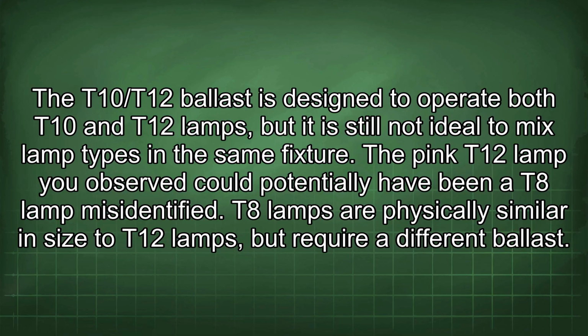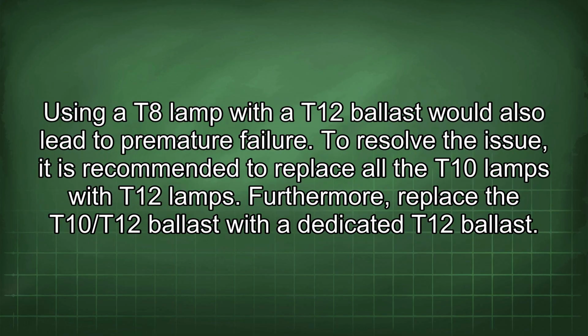The pink T12 lamp you observed could potentially have been a T8 lamp misidentified. T8 lamps are physically similar in size to T12 lamps, but require a different ballast. Using a T8 lamp with a T12 ballast would also lead to premature failure.